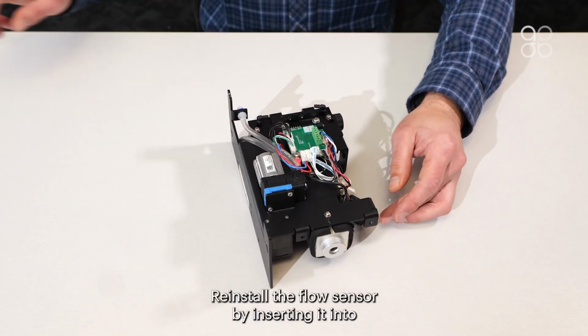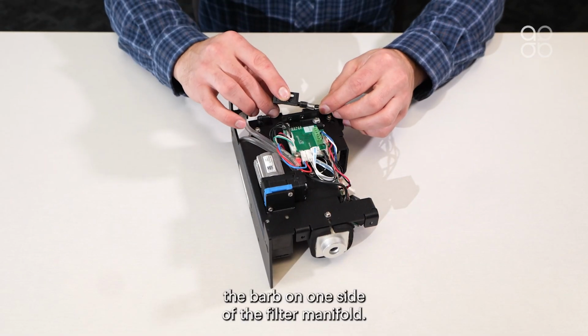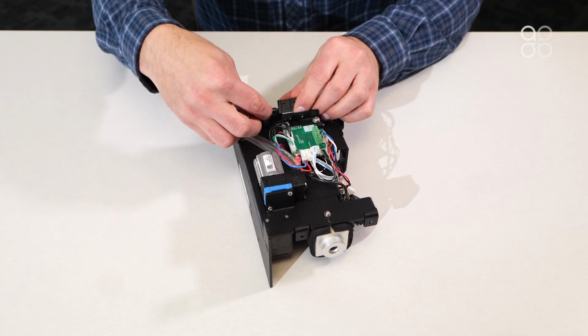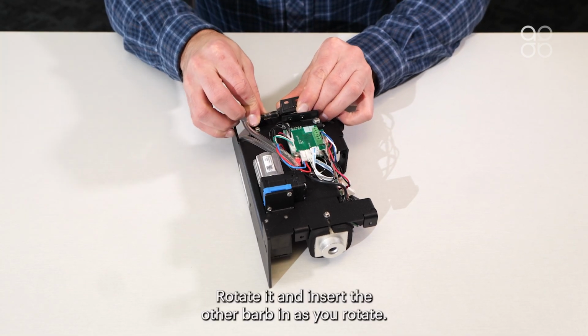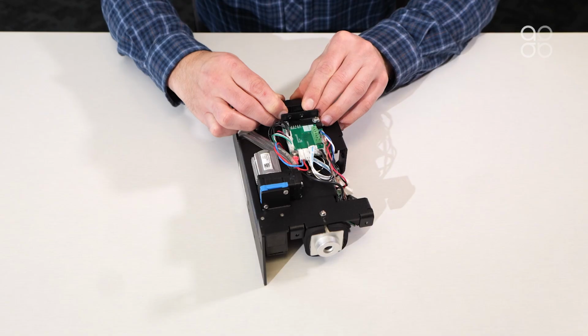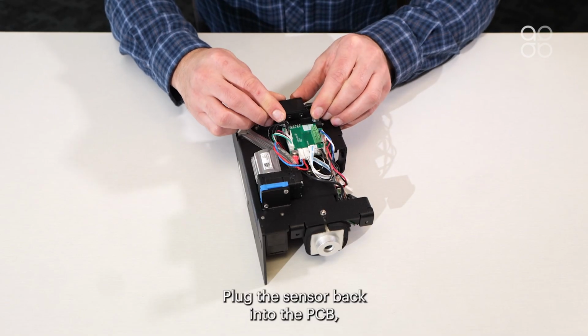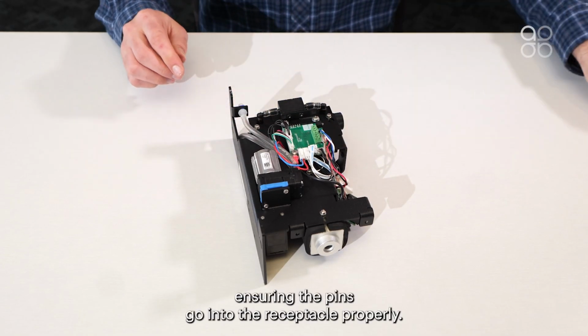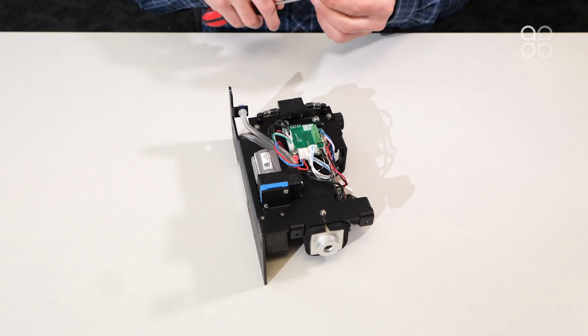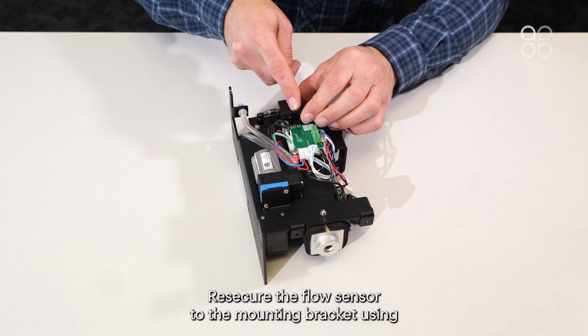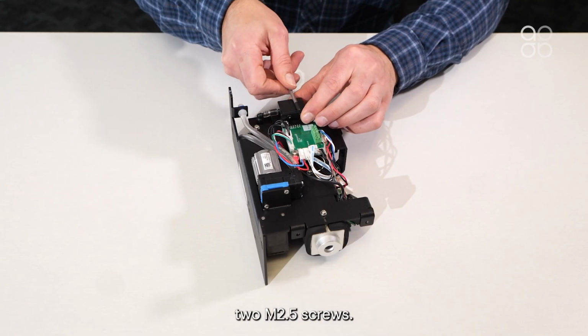Reinstall the flow sensor by inserting it into the barb on one side of the filter manifold. Rotate it and insert the other barb in as you rotate. Plug the sensor back into the PCB, ensuring the pins go into the receptacle properly. Resecure the flow sensor to the mounting bracket using two M2.5 screws.